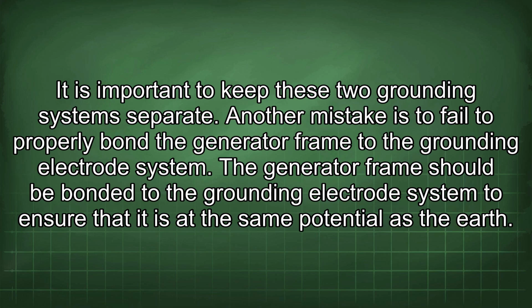Another mistake is to fail to properly bond the generator frame to the grounding electrode system. The generator frame should be bonded to the grounding electrode system to ensure that it is at the same potential as the earth.